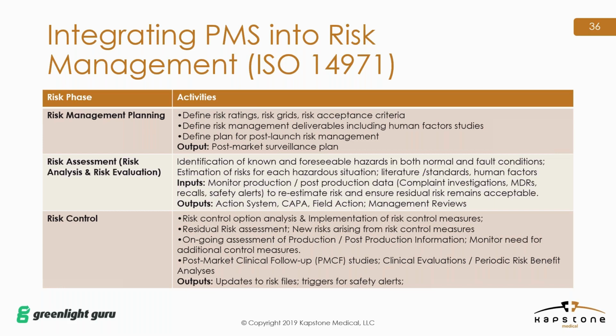You then have your risk assessment, which is your risk analysis and risk evaluation. So you've identified known and foreseeable hazards and estimated risk. Inputs into this on a continuous basis are production and post-production data, so your complaints, any reportable events, recalls, and safety alerts, and you re-estimate that risk and ensure that the residual risk remains acceptable. The outputs of this go into your quality management system. So you've used post-market surveillance data to update your risk management, and outputs could be any type of action: field action, CAPAs, incorporating this into your management review, and of course updating your post-market surveillance plan if any data is not sufficient or there are new ways of managing this data.